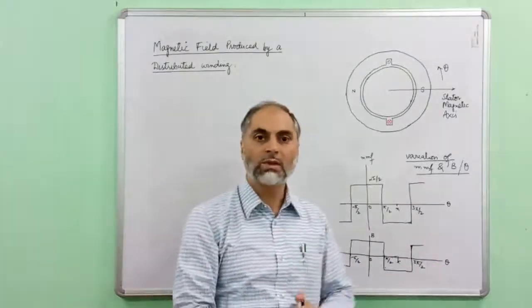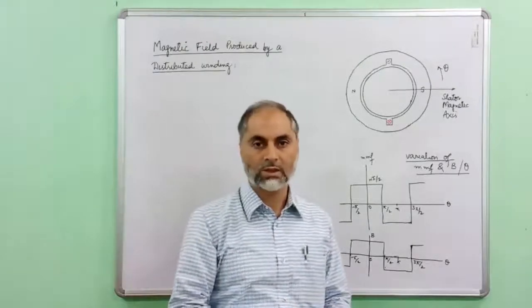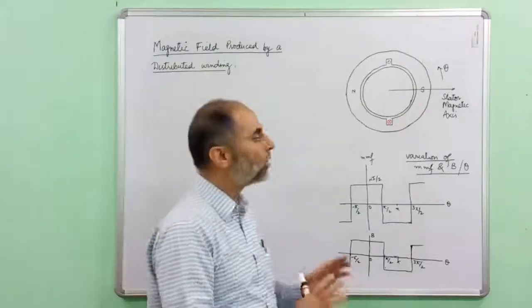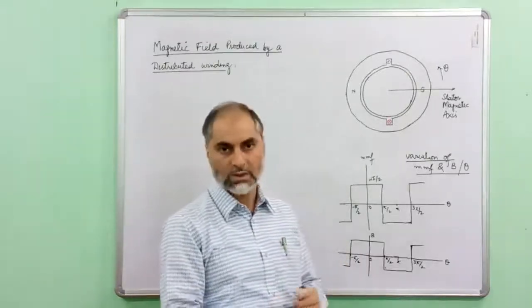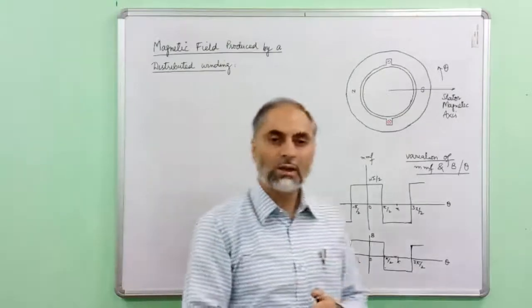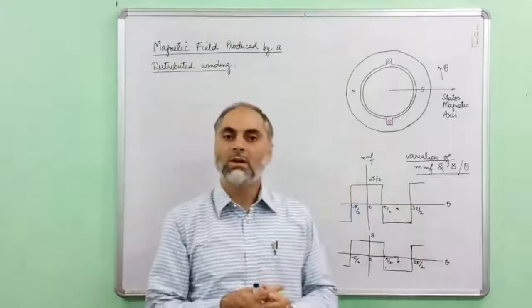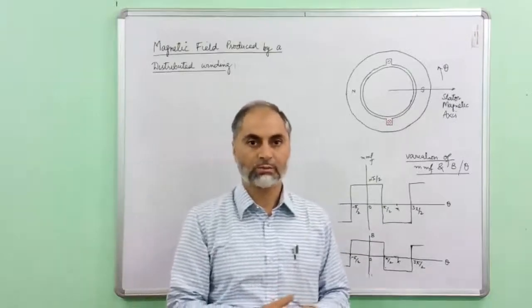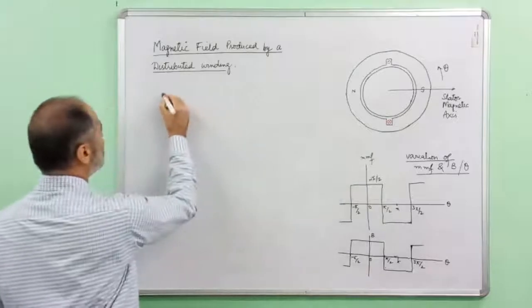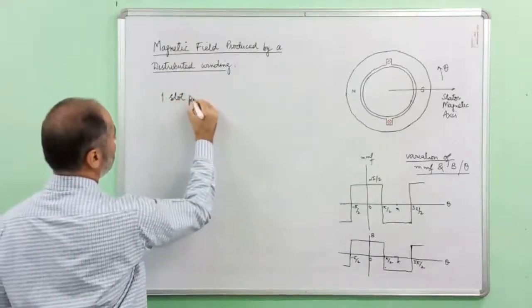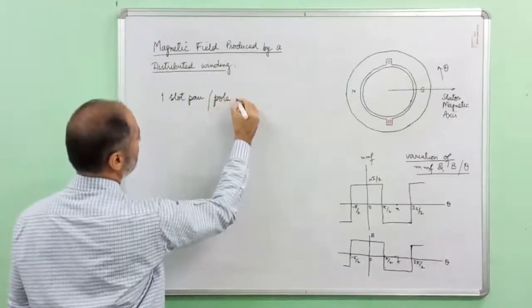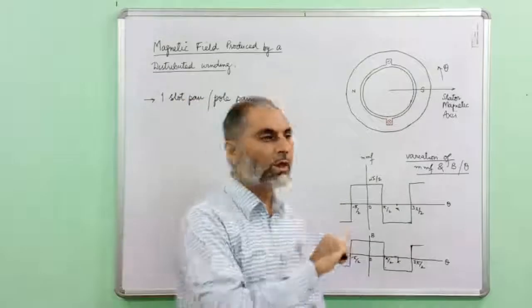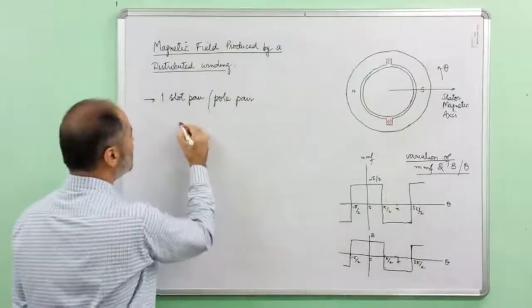In the last class we also discussed how four poles can be created on the stator. For producing four poles we need two coils accommodated in two slot pairs, and similarly for six poles we require at least three coils accommodated in three slot pairs. In all these cases we use one slot pair per pole pair, and such a winding is known as concentrated winding.